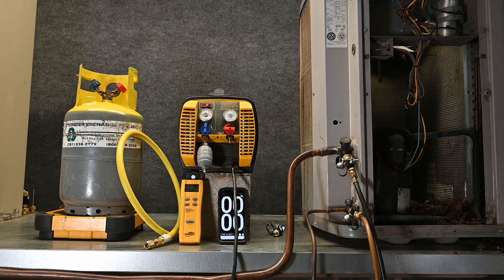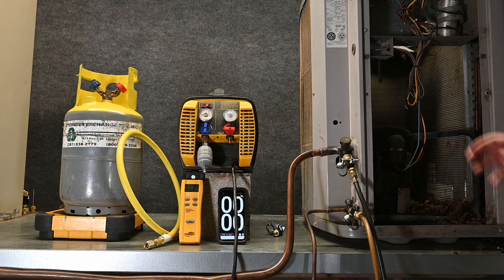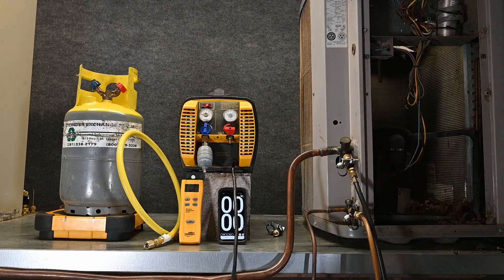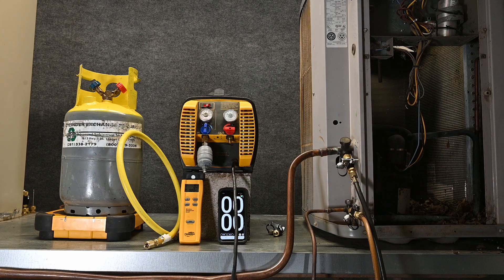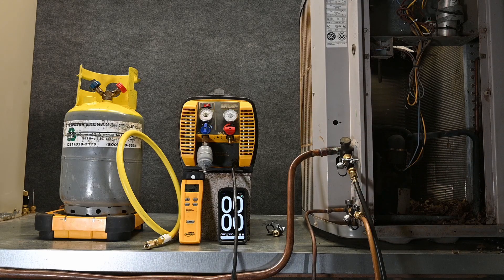Now let's look at a method called the push-pull method. Instead of using a recovery machine to push the liquid refrigerant, we're going to use a recovery machine to push vapor refrigerant.